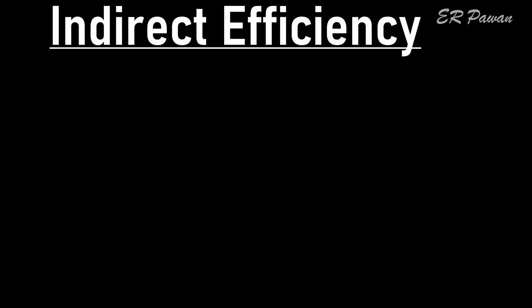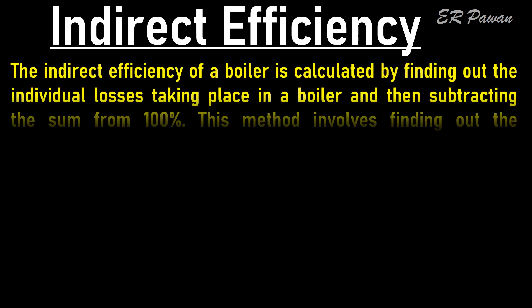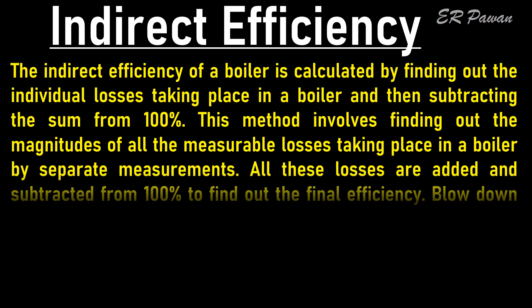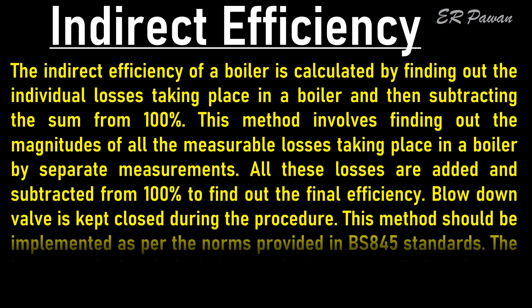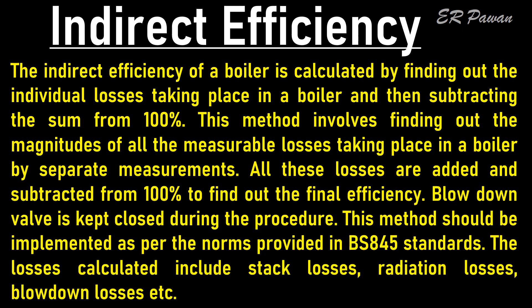Indirect efficiency: The indirect efficiency of a boiler is calculated by finding out the individual losses taking place in a boiler and then subtracting the sum from 100%. This method involves finding out the magnitudes of all measurable losses by separate measurements. All these losses are added and subtracted from 100% to find the final efficiency. The blowdown valve is kept closed during the procedure. This method should be implemented as per the norms provided in BS 845 standards. The losses calculated include stack losses, radiation losses, blowdown losses, etc.